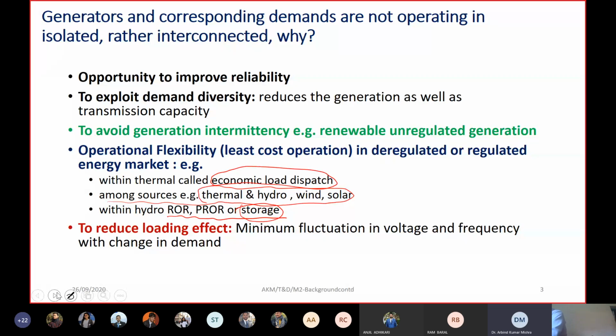Then the most important part we discussed: why we connect several generators, even if the above advantages were not there, is to have a minimum loading effect. That is, the fluctuation of voltage and frequency with varying demand. If the demand is lower, usually the voltage and frequency are higher, and if the demand is high, then both voltage and frequency tend to decrease. But this effect is relatively much lower if you share that demand by interconnecting several generators together, with respect to a single isolated generator, as we proved last time as well.